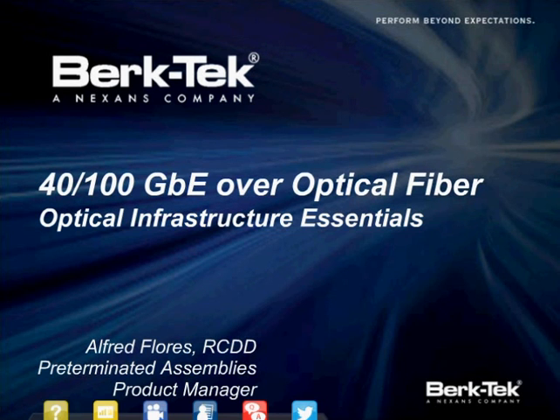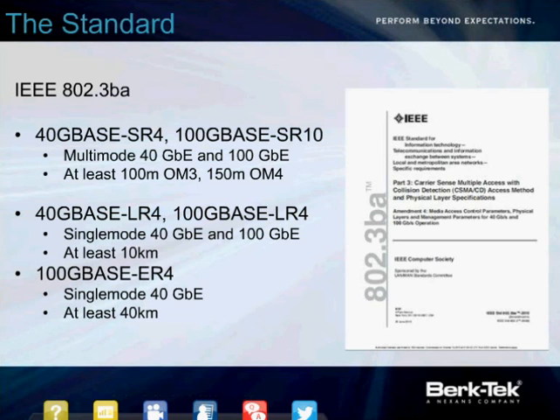As you can see from the slide, we're going to be talking about 40 and 100 gigabit optical fiber over primarily multimode and single mode. Do not disregard this — if you are looking at 40 or 100 gigabit in your future, the information shown here is essential to writing your spec. If you specify per IEEE 802.3BA, 40G base SR4, you've established the parameters. For 40/100 gigabit on multimode you need at minimum OM3 fiber, with distance capabilities up to those numbers on the chart.